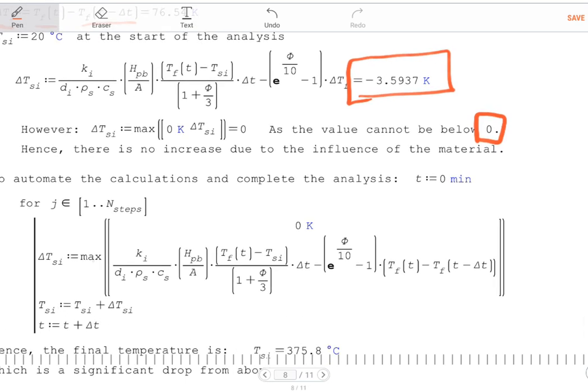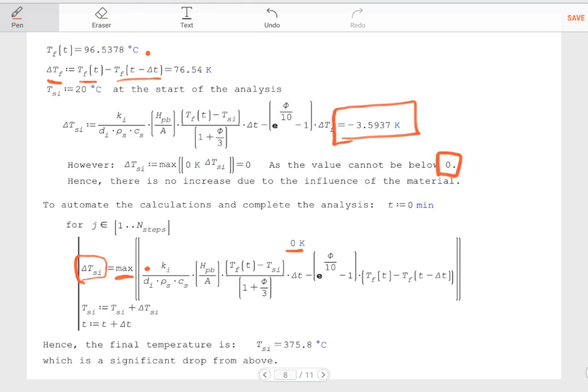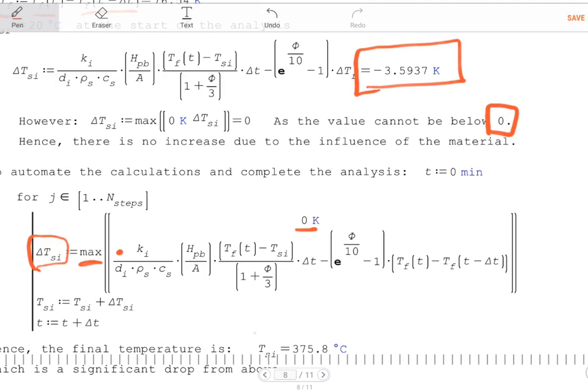So that's what I've done below. I've said use the maximum of zero, so anything below zero won't count, or the temperature increase as above. So the change in steel temperature is the maximum of zero and the calculation above. And then we loop through, carry out our 360 steps, updating the steel temperature the whole time.